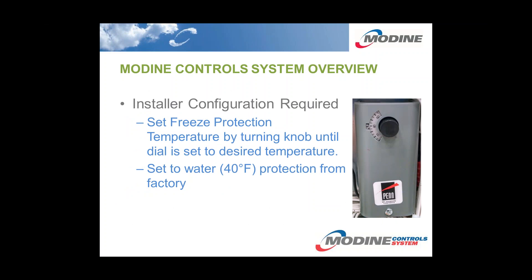The only installer configuration required, other than connecting the wires, is to set the freeze protection. There is a picture of our freeze protection controller — we've been using this for a number of years on our school products. It's a very durable, accurate, and robust controller. It is set to water protection from the factory, which is 40 degrees F, and that can be adjusted in the field by simply rotating the black knob until the dial reaches the desired position for the percent and type of antifreeze in the ground loop.